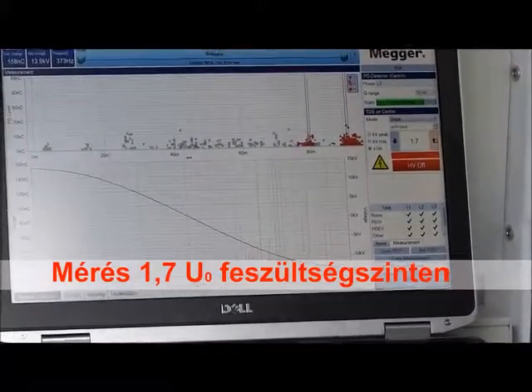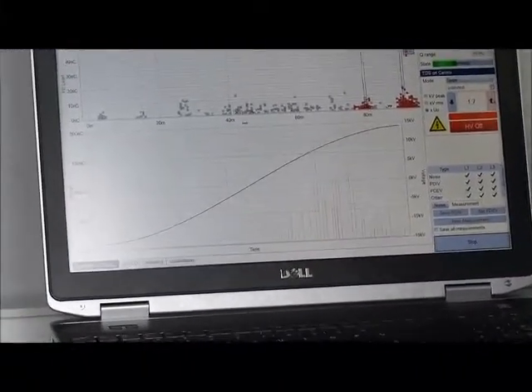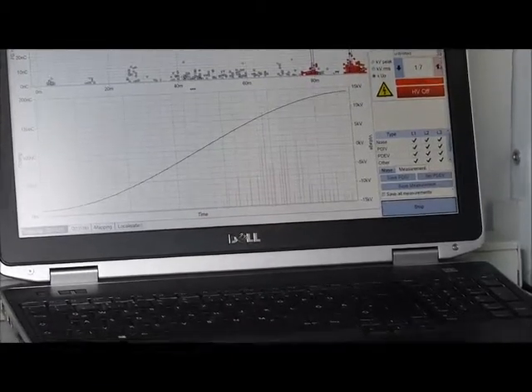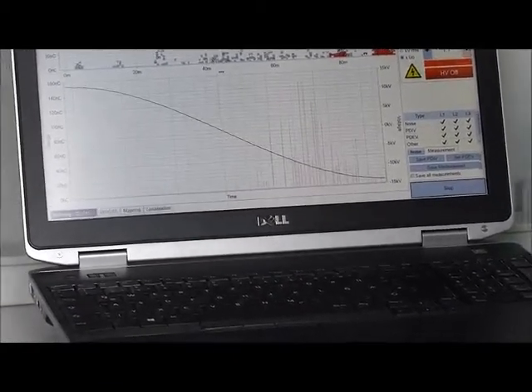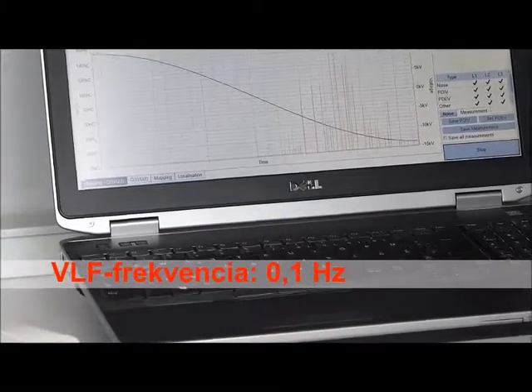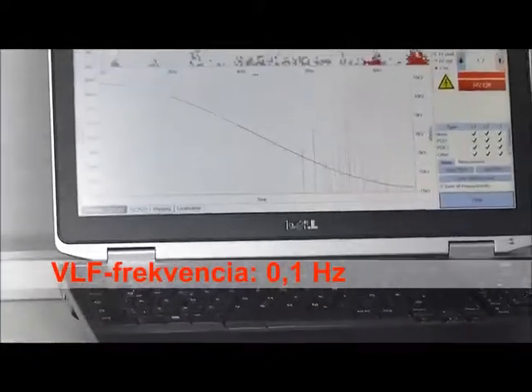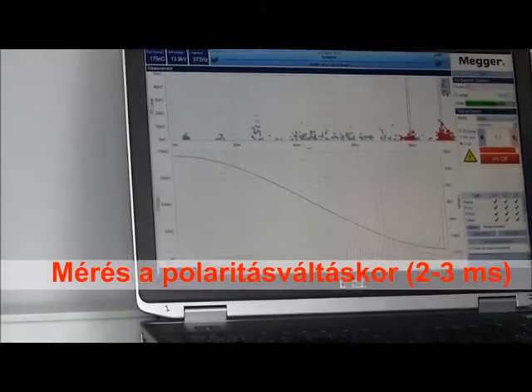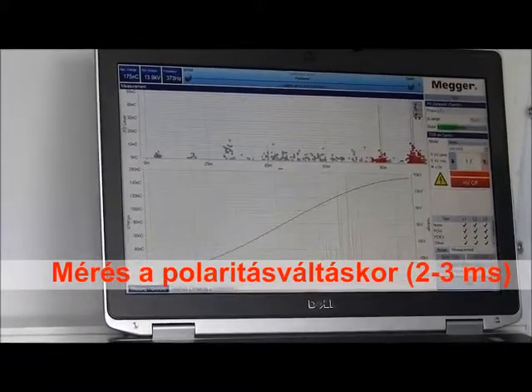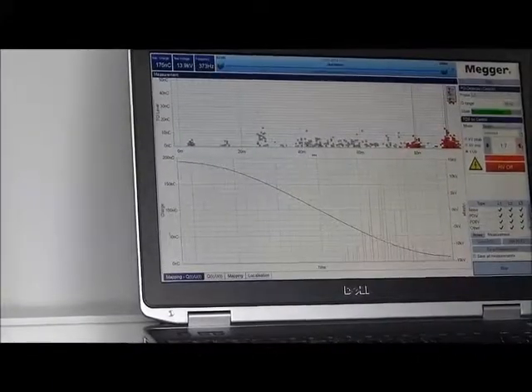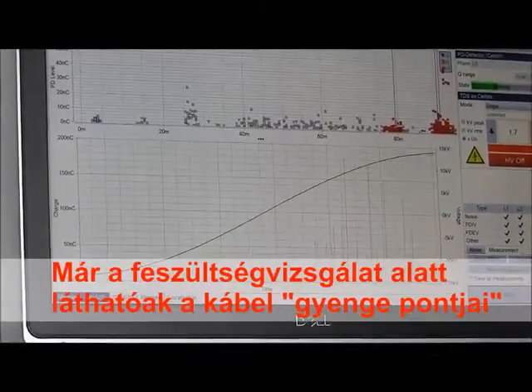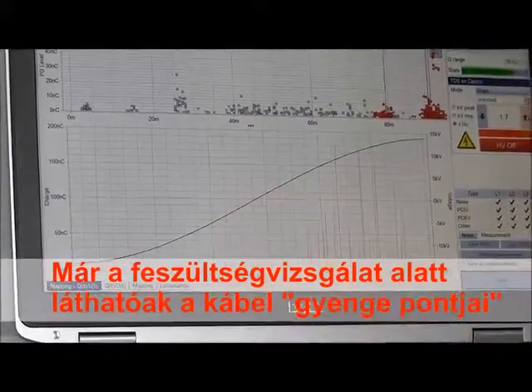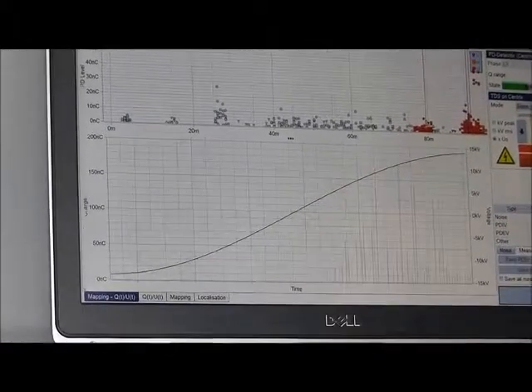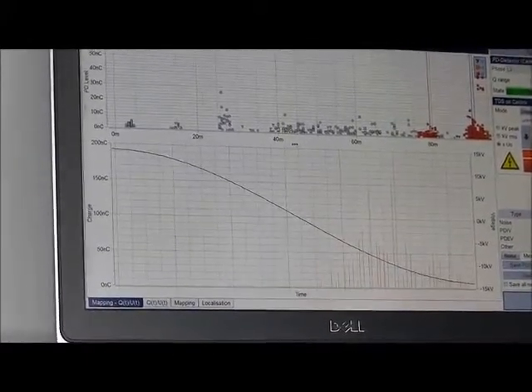Sure. So every 1 second or 2 seconds? What is the frequency? No, it's a VLF, 0.1 hertz, so 5 seconds positive, 5 negative. And only in the 2-3 milliseconds of the phase reversal we measure the partial discharges. But that's a good thing. You could do your VLF test for 60 minutes and then continuously collect the information, and additionally get the information, okay, we have some weak spot here.